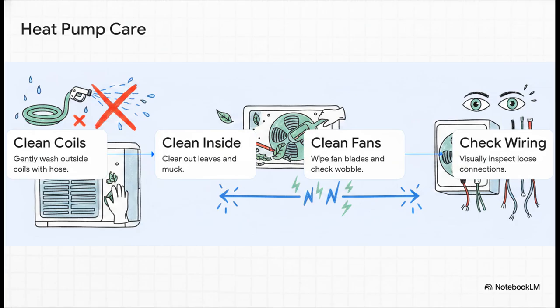For heat pumps, maintenance is a pretty straightforward sequence. First things first, always shut off the power. Then use a standard garden hose to gently wash the outside coils. Now, never use a pressure washer here. You will absolutely bend the delicate aluminum fins and ruin the whole shebang. After that, just clear out the inside muck, wipe down the fan blades, and check them for any wobble. Wobbling usually indicates a dying bearing. Finally, give the wiring a quick visual check for any loose connections.